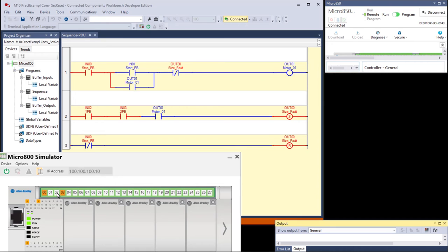Again, the operator comes over. He or she could just push the carton forward out of 1PE and then reset it and clear the fault. And it would start up again with the rogue carton in there. You can't just keep adding stuff to make this idiot-proof. Add some logic that won't allow you to reset unless both photo eyes are clear. Now, I know that's not in the manual, but as long as we're exploring this, let's check that out.